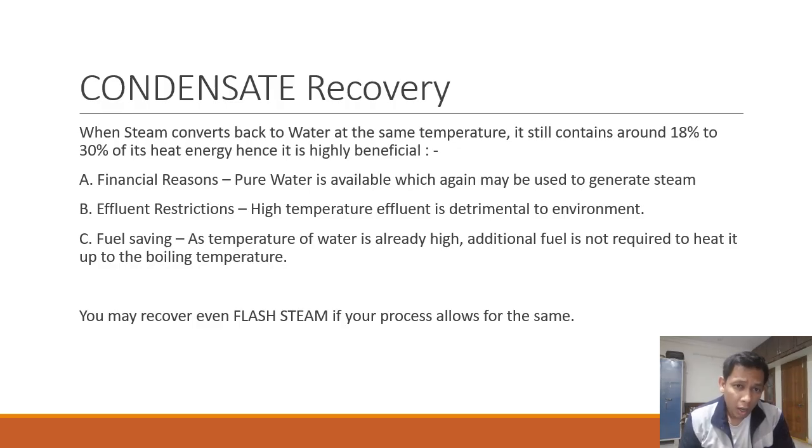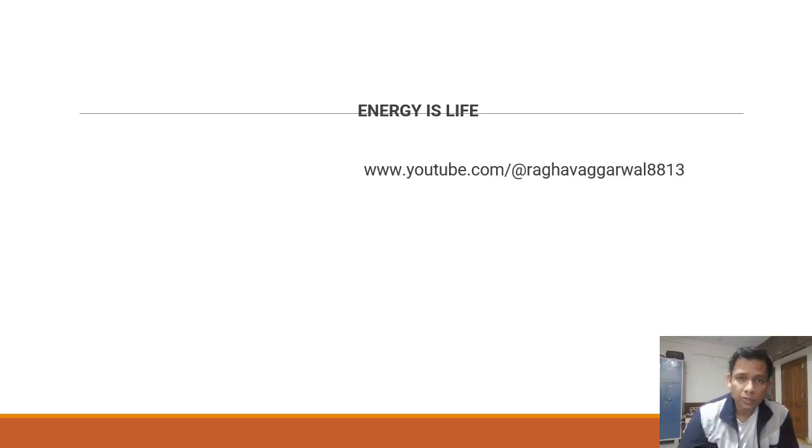Moreover, high temperature effluent is very detrimental to the environment, so there are effluent restrictions. And the third thing is fuel savings. The higher the temperature of the water already available, the lesser is the amount of fuel you need to spend to heat it again to the boiling temperature. And one more catch is there, you can even recover flash steam from the water if your process allows for it. And we may discuss it in some later video.